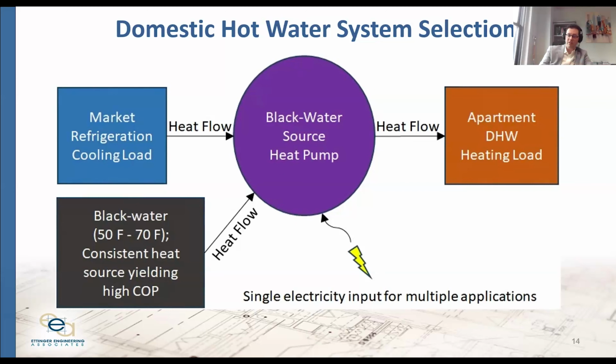With a blackwater source heat pump in a residential building and other typologies, we can really come closer to achieving circularity. When we take the waste stream — literally the sanitary sewer waste off the apartments, what's coming out of shower drains, toilets, sinks, washing machines and dishwashers — sewers run consistently between 50 and 70 degrees. So as long as we're in the building doing our thing, the blackwater source exists.